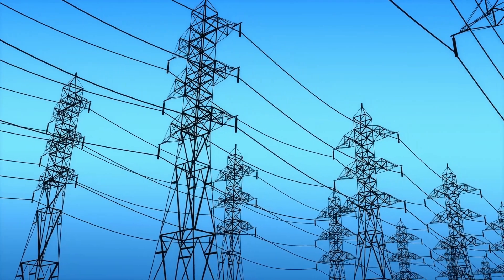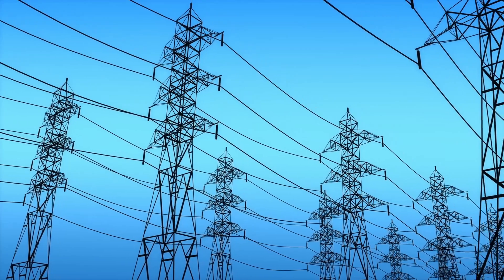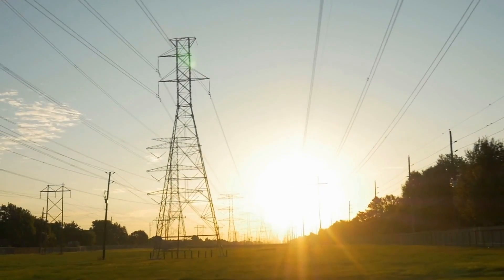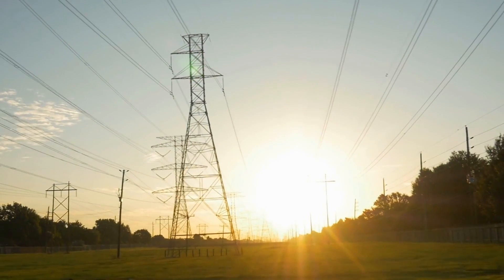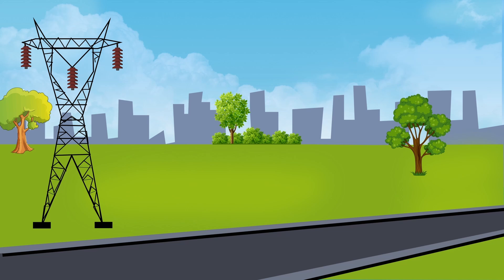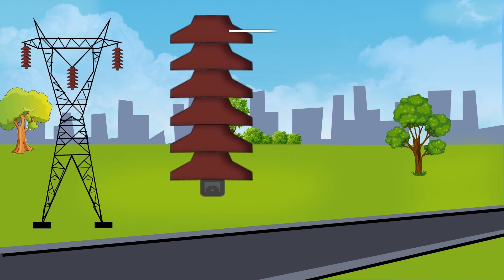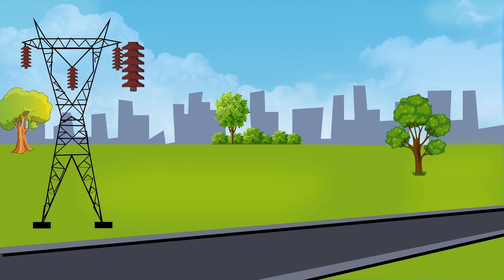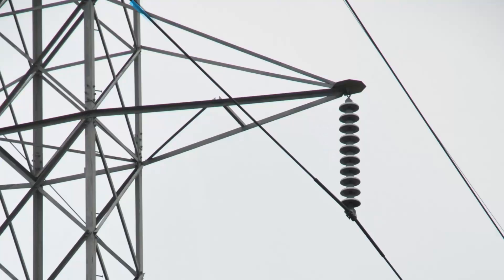As mentioned earlier, beyond 33 kV we cannot use pin type insulators. So, for high voltages, suspension type insulators are used. They are generally used with steel towers. A suspension type insulator consists of several insulator discs connected in series by metal links in the form of a string.